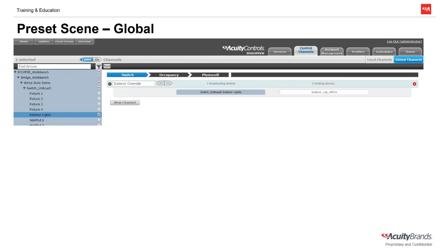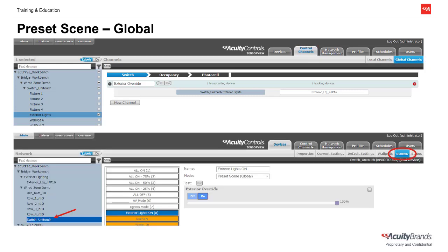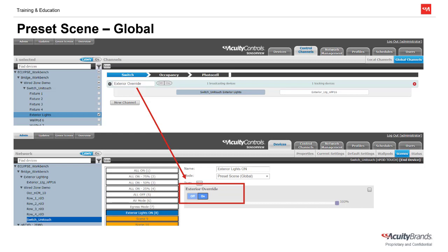Now let's take a look at Global Preset Scenes. Like a Local Preset Scene, the Global Channel must be created prior to being able to select that channel as part of your Global Preset Scene. Creating Global Channels is covered in a separate tutorial. Still under Scenes for the nPod Touch, you can see we now have the mode set to Preset Scene Global. This will allow you to add in any pre-programmed Global Channels you're trying to control with this scene. We added our Exterior Override Channel and set it to 100%. After naming and saving, we will now have a button in a separate control zone to turn on our exterior lights to 100%.